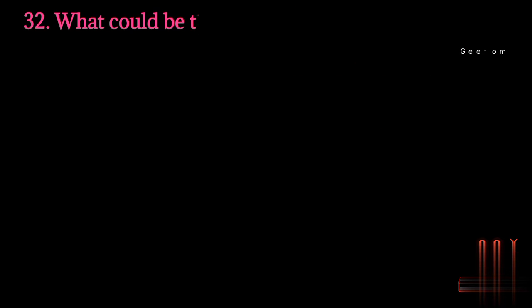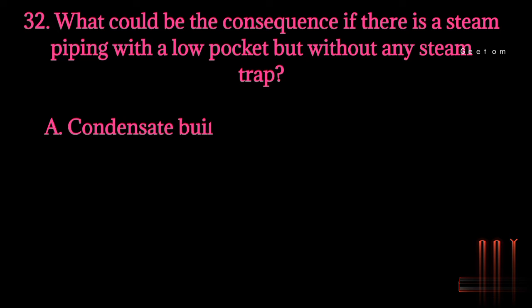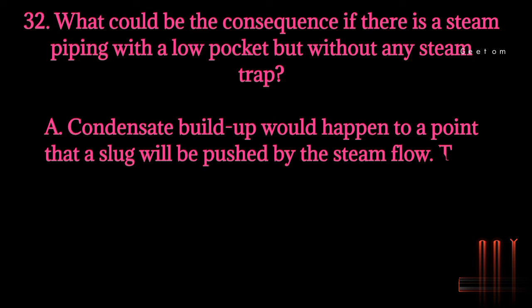Question 32: What could be the consequence if there is a steam piping with a low pocket but without any steam trap? Answer: Condensate buildup would happen to a point that a slug will be pushed by the steam flow. This slug of condensate could cause water hammer and it could damage the piping.